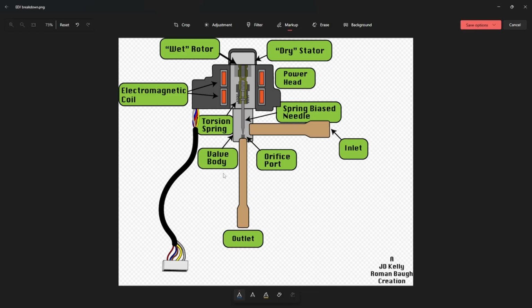On top of the resistance checks, there are DC volt checks you can do as well if you want to test it while it's running and while it's powered. Those are a little trickier, and the DC voltages vary from manufacturer to manufacturer. To be honest, I've never bothered with the DC volt checks on Trane's stepper motors because the resistance checks are pretty foolproof. The majority of the time you have an issue with these stepper motors, it's going to be a failed coil. Again, most of the time, the valve body isn't going to have an issue with it. If it will have an issue with it, you can usually tell that by taking a temperature difference from the inlet of the stepper motor, so the liquid line going into the valve body, to the outlet or to the inlet of the coil.